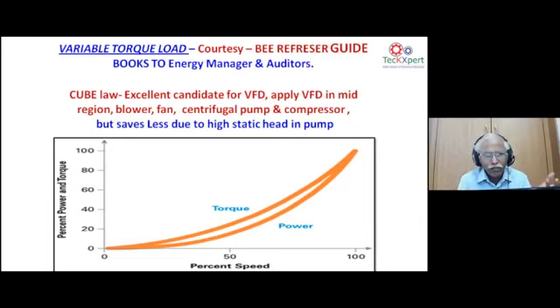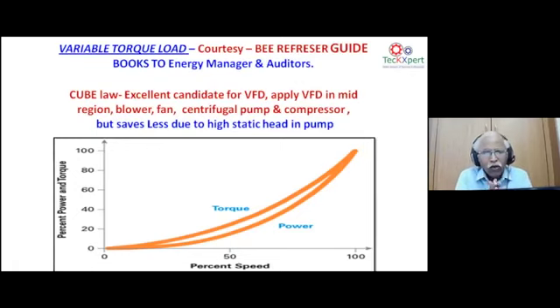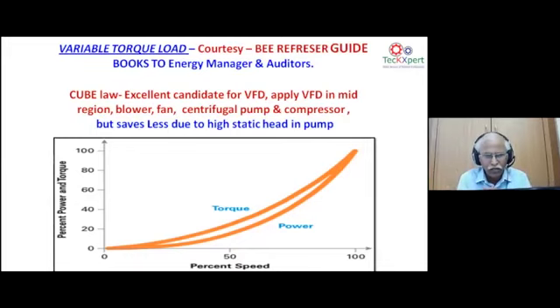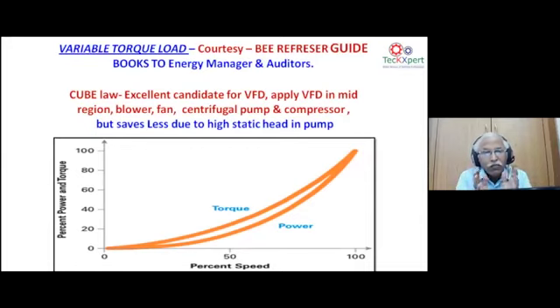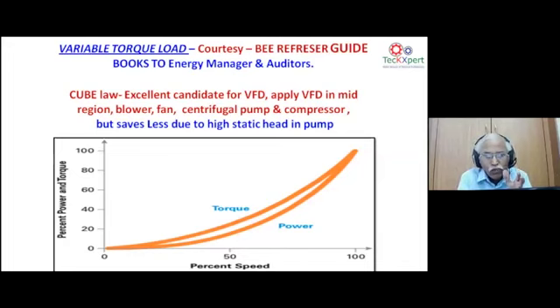The cube law makes VFD an excellent candidate for centrifugal blowers, especially backward-curved types — where even if throttled, power automatically comes down. Torque and power go together in variable torque operation. This is the main application for centrifugal blowers where energy optimization through VFD offers significant savings.